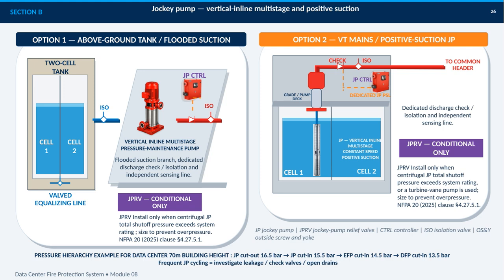The pressure hierarchy shown for a 70-meter data center building is also important. The jockey pump cuts out at 16.5 bar, cuts in at 15.5, the electric fire pump cuts in at 14.5, and the diesel fire pump at 13.5. Frequent jockey pump cycling is a warning to investigate leakage, check valves, or open drains. Finally, the jockey pump relief valve is conditional. It is required only when shutoff pressure could exceed the system rating, or when a turbine vane pump is used, and it must be sized to prevent overpressure.